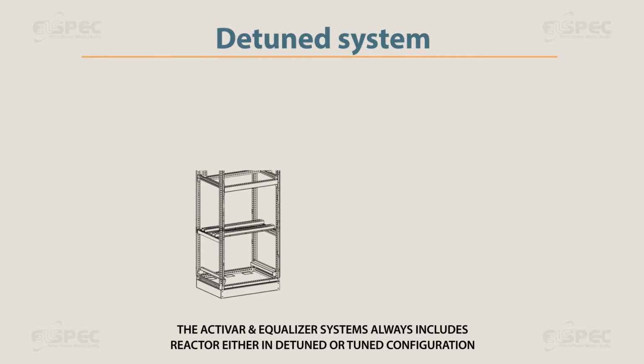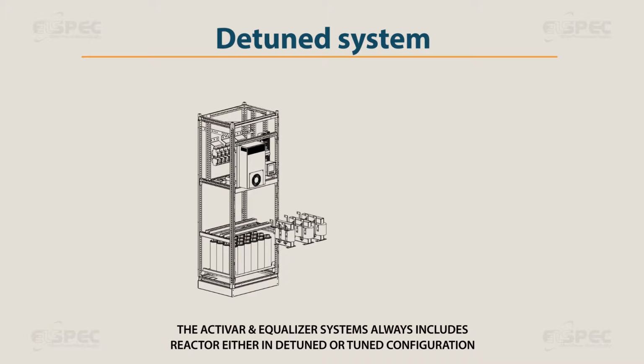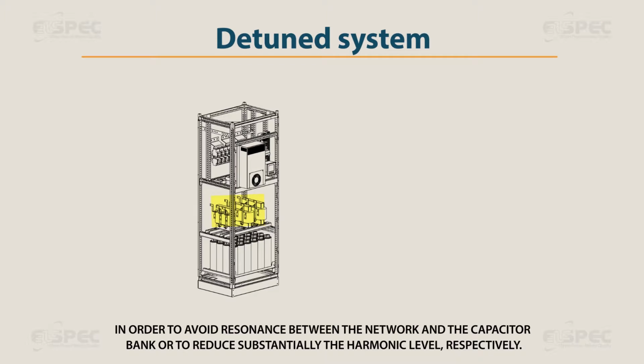The Activar and equalizer systems always include a reactor, either in detuned or tuned configuration, in order to avoid resonance between the network and capacitor bank, or to reduce substantially the harmonic level, respectively.